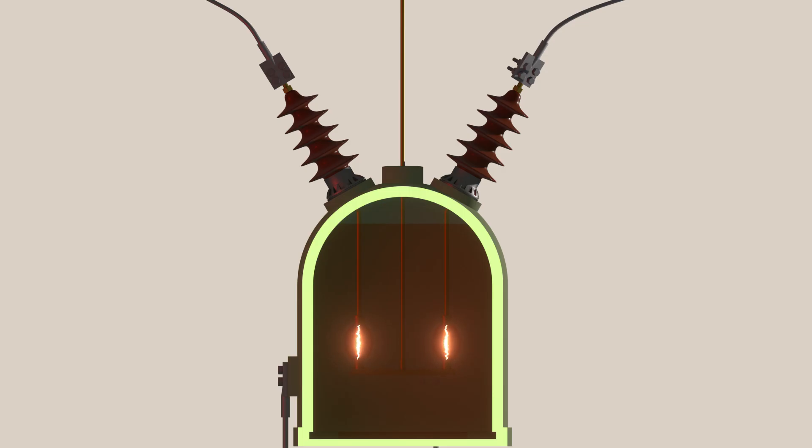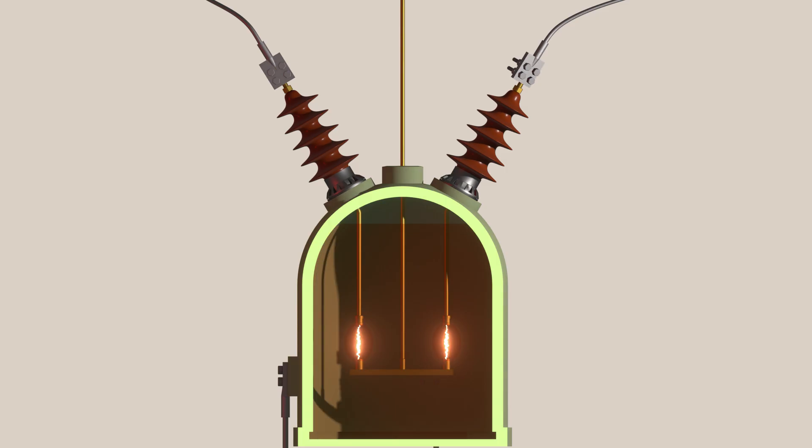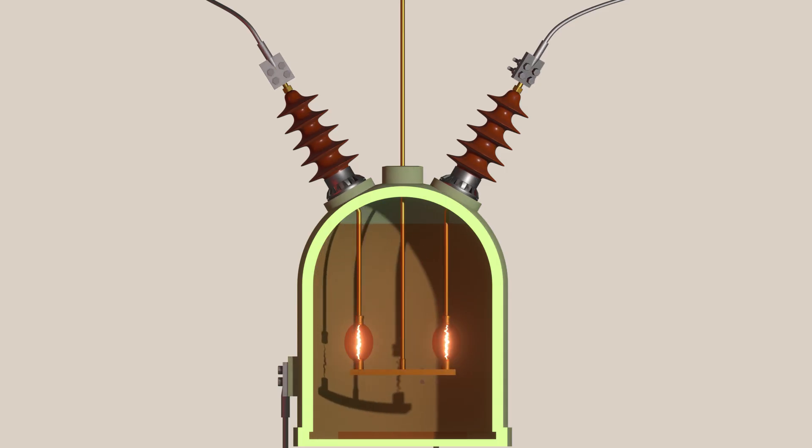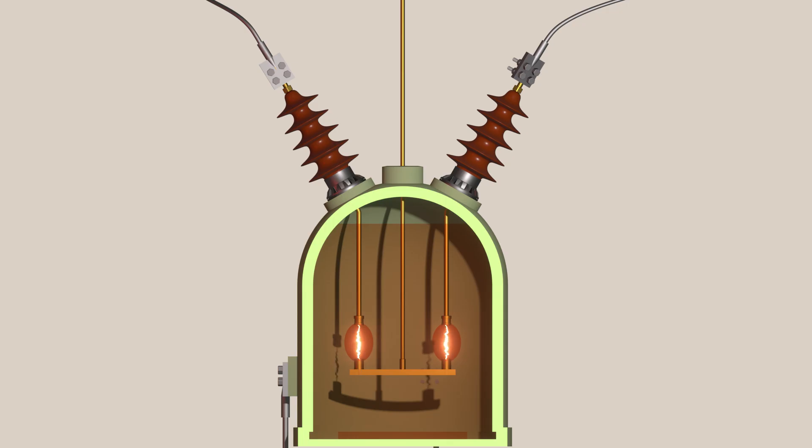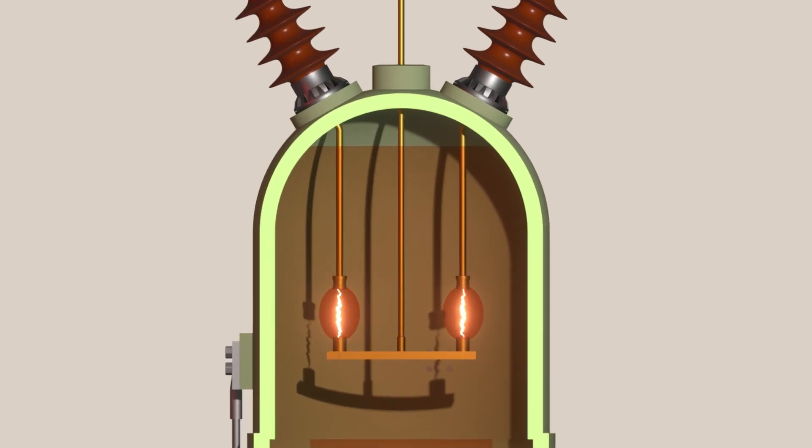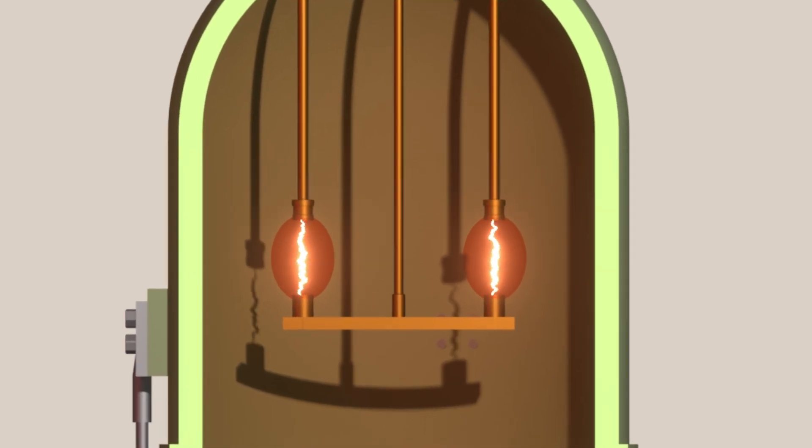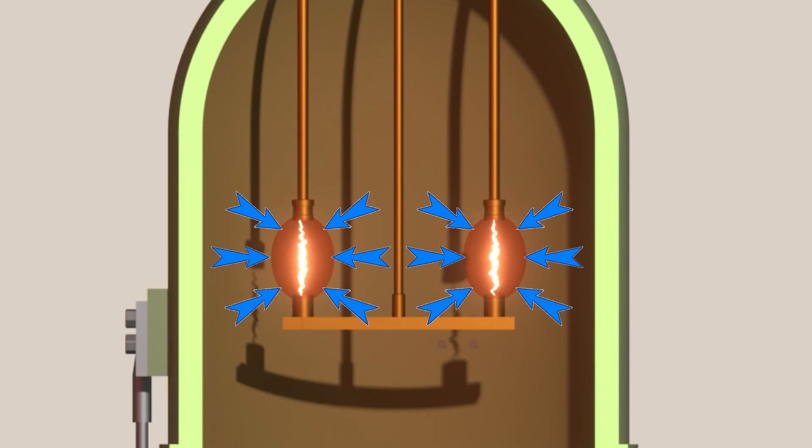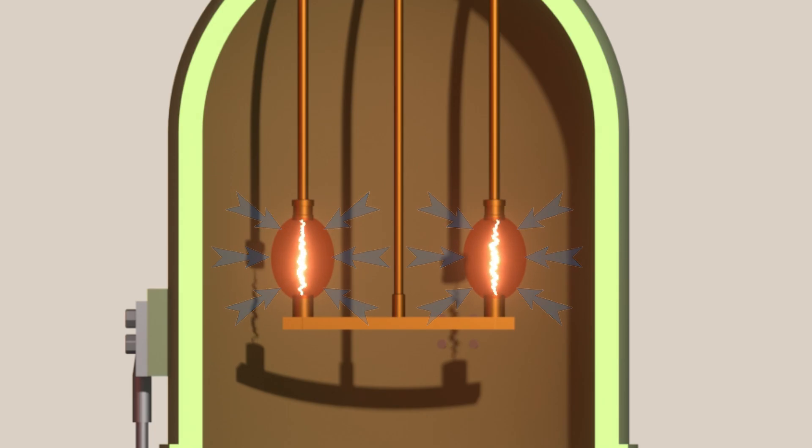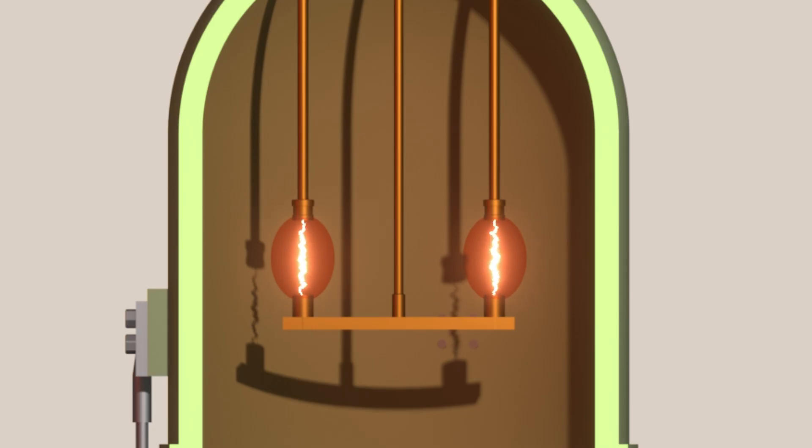The surrounding oil vaporizes and decomposes, generating hydrogen gas. As oil is a hydrocarbon, this hydrogen gas forms a gaseous bubble around the arc. The surrounding oil applies high pressure to this hydrogen bubble. As the arc continues, more oil decomposes into hydrogen gas, and the bubble size tries to increase.